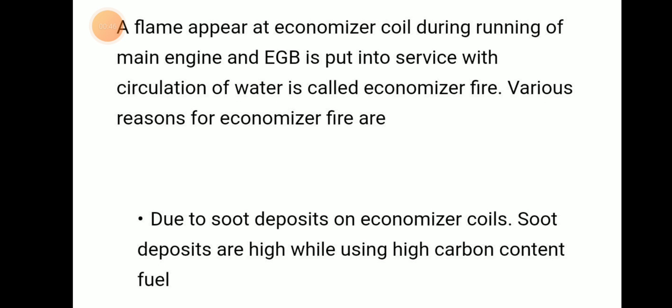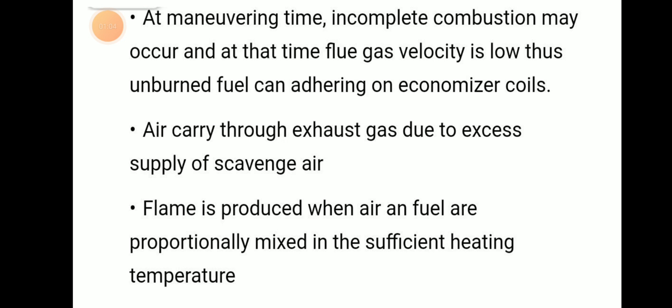The causes of economizer fire include soot deposits on the economizer coil. Soot deposits are high when using high carbon content fuel. Due to soot deposits on the economizer coil, the soot deposit will be high when using high carbon content fuel.